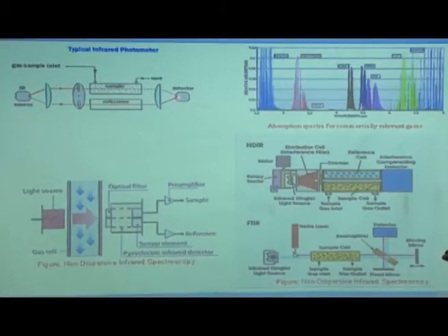Then it is focused through a lens onto a detector. The detector is basically a cell which is divided in half by a thin diaphragm, and it has only carbon monoxide on both sides. Okay. So, now here the wavelength characteristic of carbon monoxide is not absorbed at all, here some of it is absorbed. So, the energy going in from this direction will be higher, the energy going in from this direction will be less.